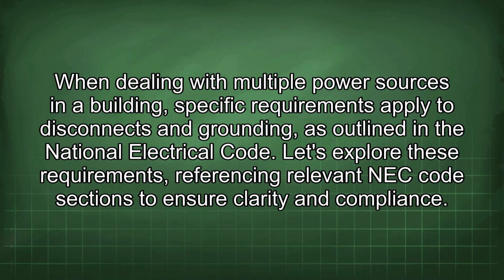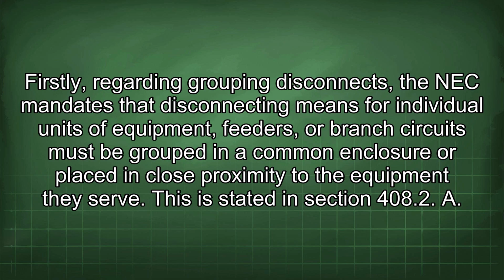When dealing with multiple power sources in a building, specific requirements apply to disconnects and grounding, as outlined in the National Electrical Code. Let's explore these requirements referencing relevant NEC code sections to ensure clarity and compliance. Firstly, regarding grouping disconnects, the NEC mandates that disconnecting means for individual units of equipment, feeders, or branch circuits must be grouped in a common enclosure or placed in close proximity to the equipment they serve.